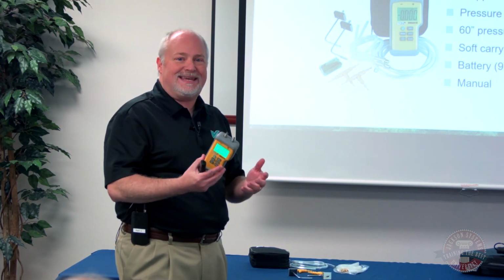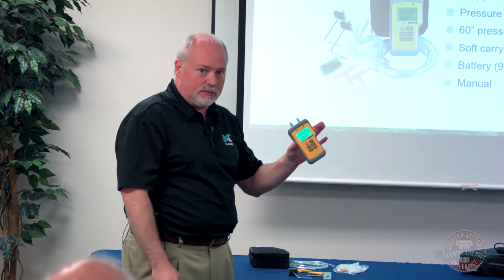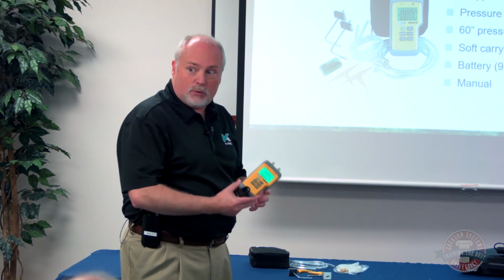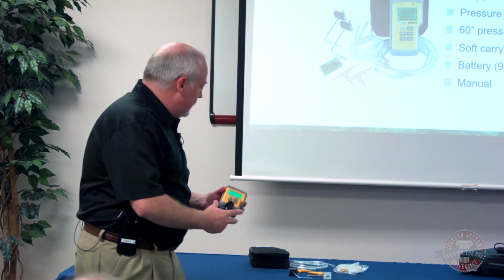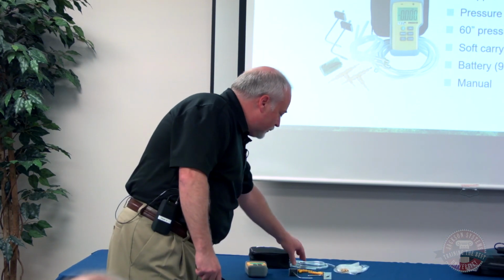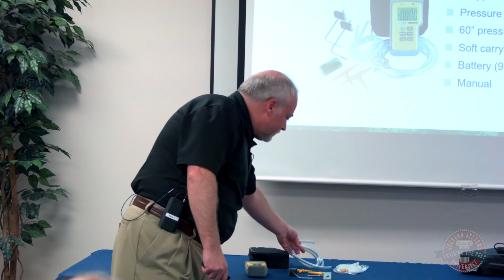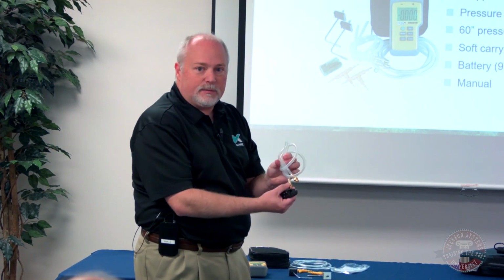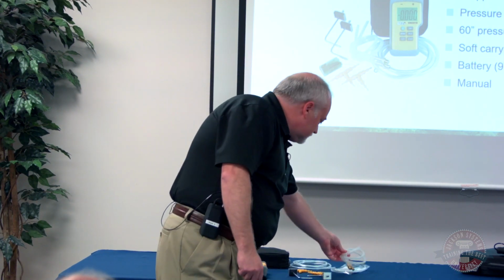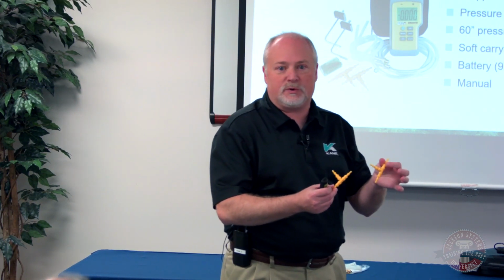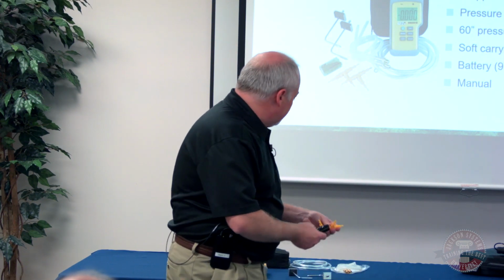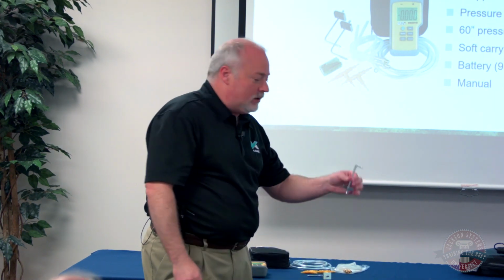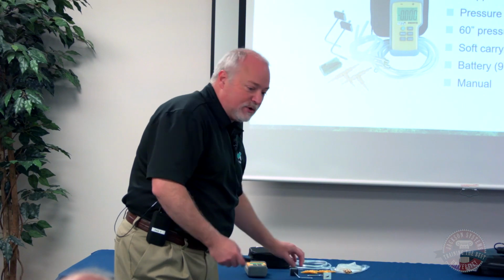So what all comes in the kit when you purchase the EM201SP kit? This is available just as a manometer, but it gets a lot more useful when you buy the kit that comes with some extra tubing. We've got barb fittings to be able to check our gas pressure. We've got stepped T's that we can use for checking pressure switches, which we'll talk about a little bit later on. And as well, external static pressure probes. And we'll talk about the application of these and why these are important for some of your readings.